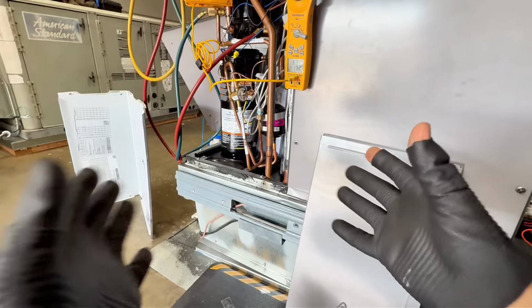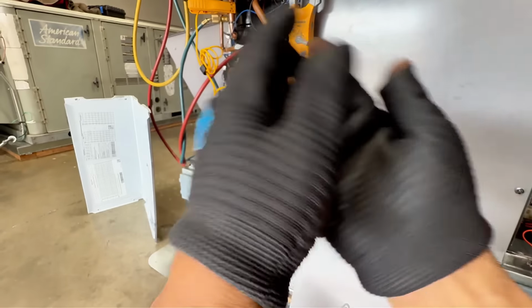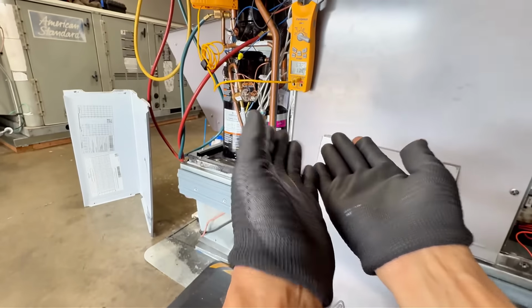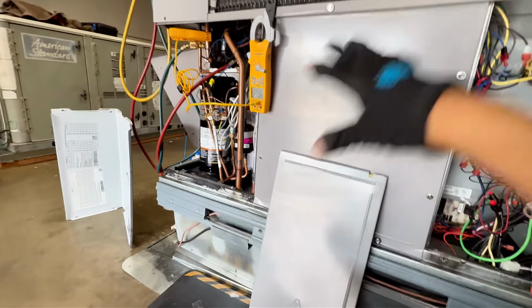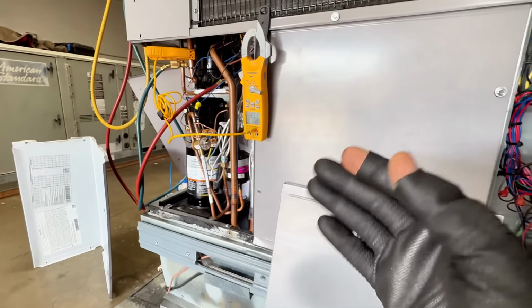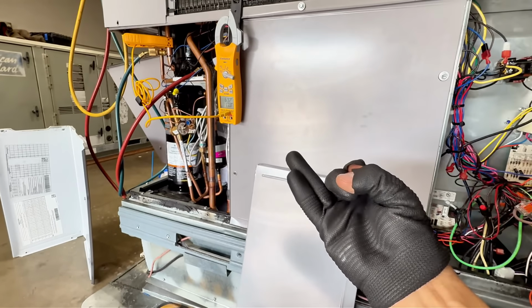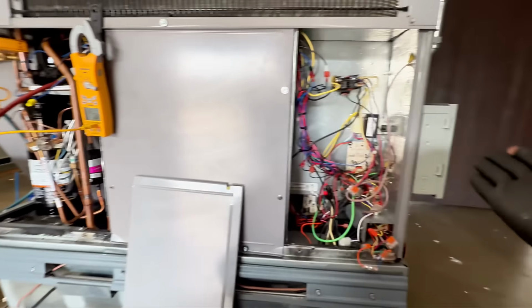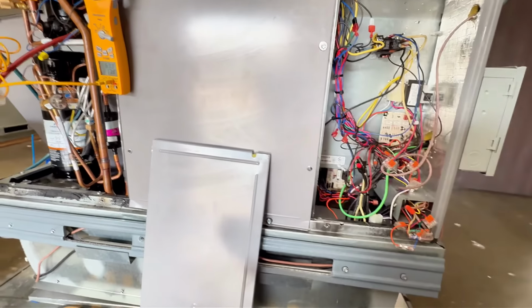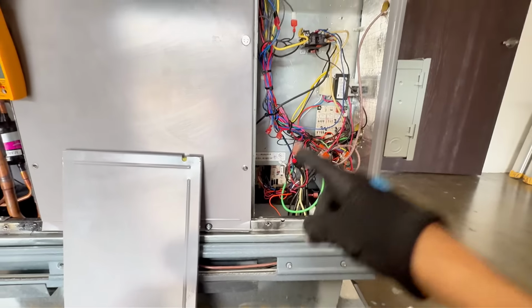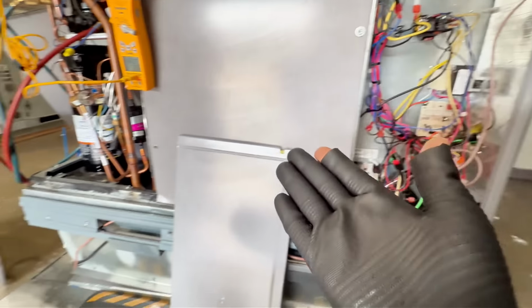No, it's not about that. The compressor might be just fine. It might be just low on charge, or it could be a bad cap. So I'm not going to be checking that right away. I'm going to check it if a breaker tripped or the fuses went bad. But in this case, we didn't have that, and I didn't smell anything. You use your senses. In this case, the low voltage was not making it back to the contactor coil.